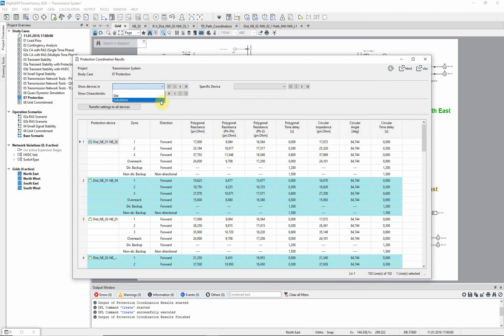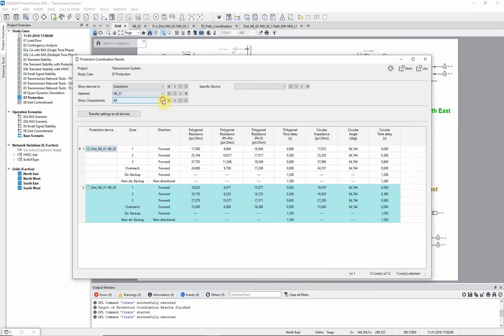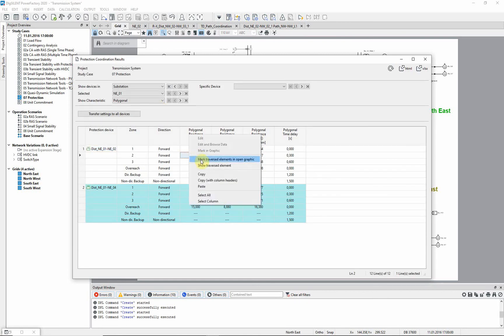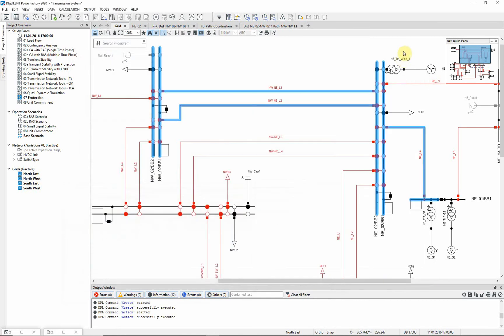Let us filter according to substations and polygonal characteristic, and mark the traversed elements for the zone 2 reactances of the first relay. As you can see, the zone 2 settings were determined using the first line and the shortest of the adjacent lines.